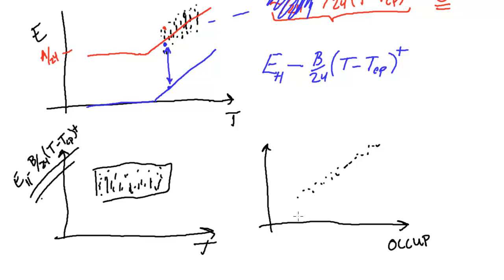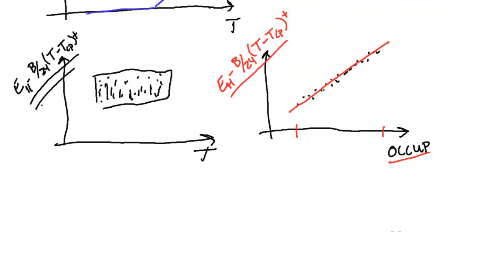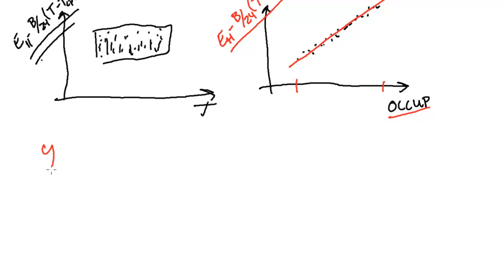If it's very low, that could be night time. And so, here, when we have low occupancy, we might have a lower residual, because we're lower in the energy, and higher in occupancy. And if this is linearly related, now we can go ahead and this still is this hourly residual. We can go ahead and regress this. Where now this is your Y, and this is your X. So, if we do a straight line, for instance, Y equals mx plus b, we'll call, we're going to give these new names.